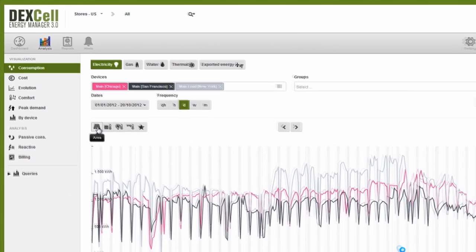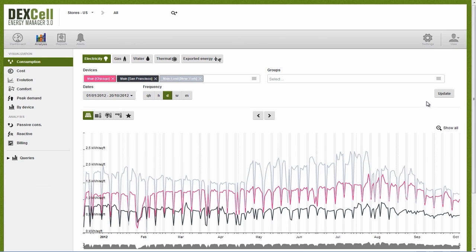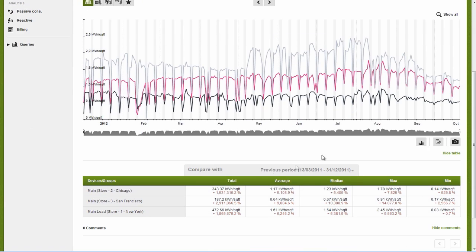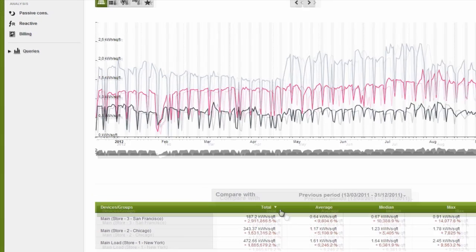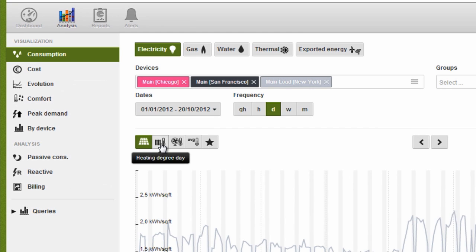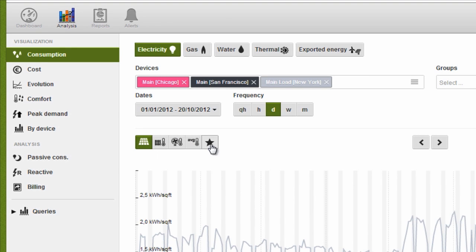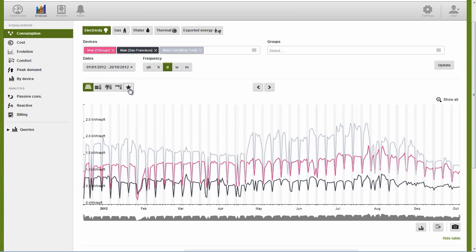For example, when we factor in the surface area of the stores, we see that the Chicago supermarket, which originally ranked first for energy efficiency, falls to second place and the San Francisco store comes in first. We can filter our original results by entering a wide range of ratios like degree days, average temperatures, tickets, occupancy levels, average sales, or anything else that might be useful to understanding exactly what is affecting consumption.